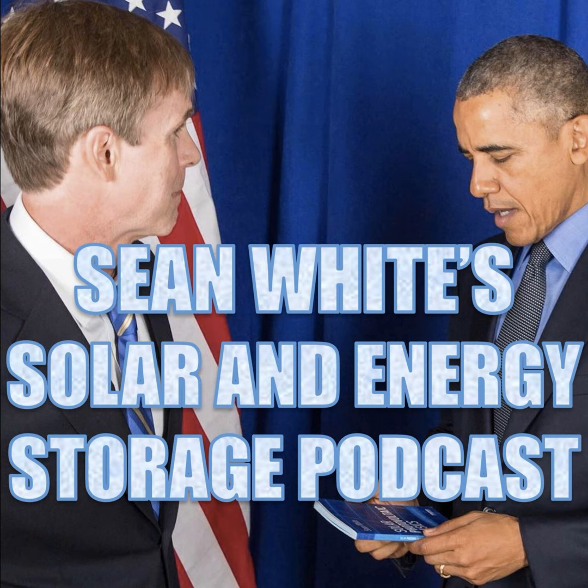Okay, on to part 4 of Article 706, Energy Storage Systems, which is flow battery energy storage systems. And so we are not going to Article 480 for sure with flow batteries. And let's see what else we're going to refer to, which is, hint, Article 692. All electrical connections to and from the system components shall be in accordance with the provisions of Article 692. Guess what that is? Fuel cells. So a flow battery is sort of like a fuel cell. So we're going to take our flow batteries and treat them like fuel cells. And fuel cell systems is Article 692.